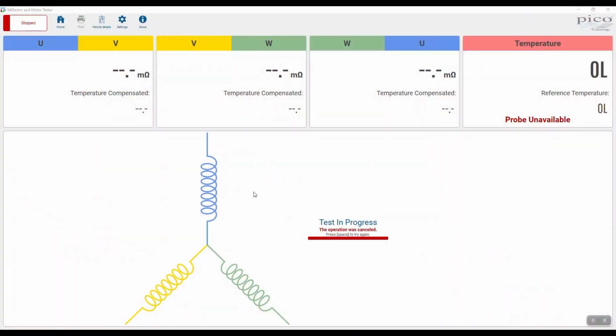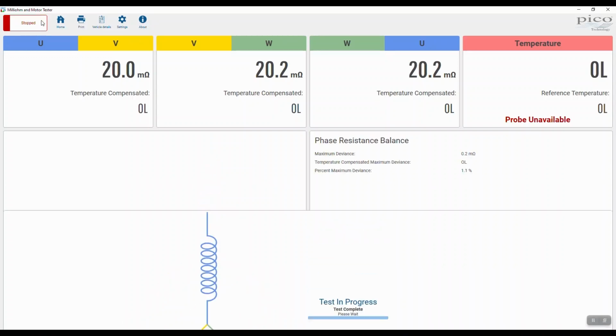So let's run the test now, which is a super non-intrusive test, because we want to be assured that the windings on this are correct before we actually install. The temperature probe is not connected at the moment. This is just a quick test to evaluate winding resistance. So that's good, that's a good start. Hopefully we should see something similar now. Excellent. And then fingers crossed for the final winding. And there we go.